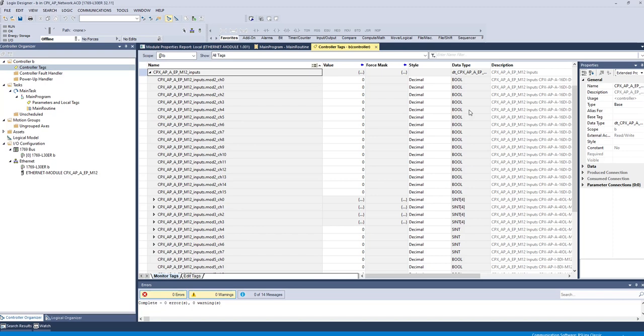Here, looking at a 16 digital input module, these are all booleans, going from 0 to 15. And that was the first device on the AP-A manifold. The second device was that I/O link master. So here is the AP4IOL, which is an I/O link master. We defined it to be 4 bytes of data, so it's a cint with an array of 4 for each of the channels, 0, 1, 2, and 3.